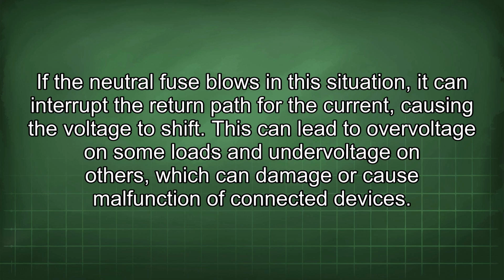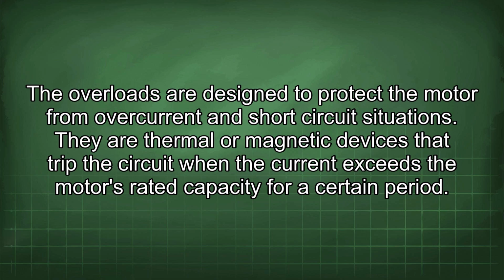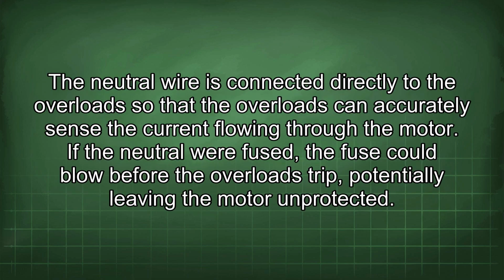of connected devices. The overloads are designed to protect the motor from overcurrent and short-circuit situations. They are thermal or magnetic devices that trip the circuit when the current exceeds the motor's rated capacity for a certain period. The neutral wire is connected directly to the overloads so that the overloads can accurately sense the current flowing through the motor.